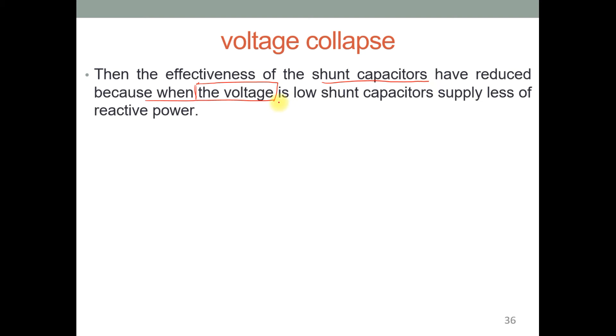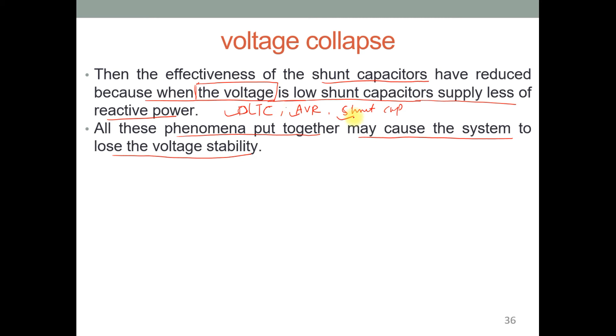Clear? So all these phenomena put together make the system lose voltage stability. Clear? All this sequence, starting from this transmission line outage and then OLTC not being in a position, then AVR and compensating devices, and yes, shunt capacitors, these all have reached their maximum limit to regulate the voltage in the system. And all these phenomena put together make the system lose voltage stability because all the regulating devices are not in a position to regulate the voltage at the generator side or at the transmission side.